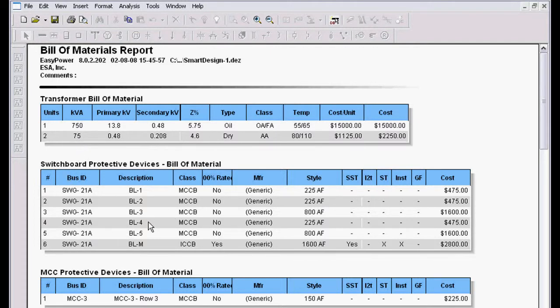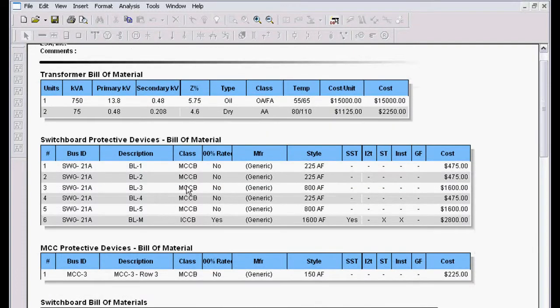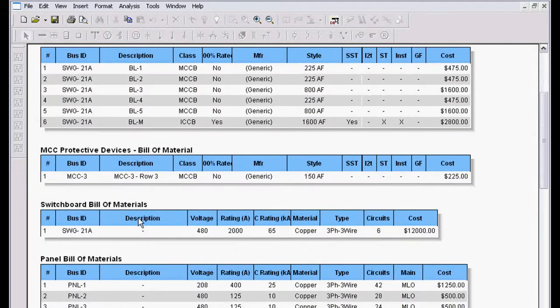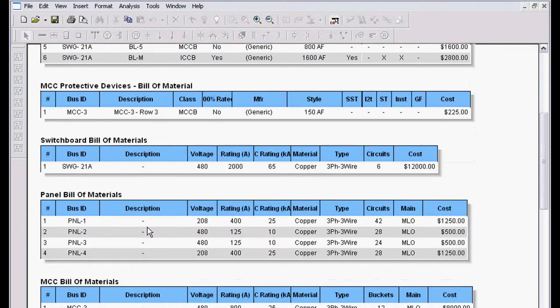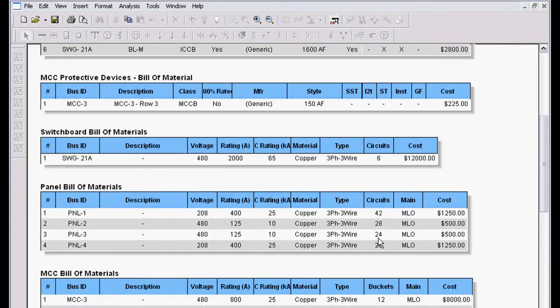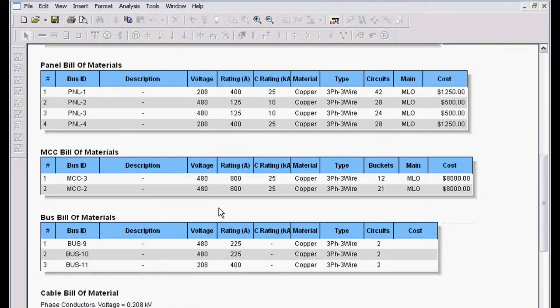Here's our switchboard that was selected, and all the breakers in the switchboard. It even tells us what trip functions that they have. So this is a complete generic specification that we can go out to bid with. It gives me my switchboard bill of materials, my panel bill of materials, how many at 208 volts, how many at 480. If they're 3 phase, 3 wire or 4 wire, number of circuits, main lug only, or main breakers. MCC bill of materials.